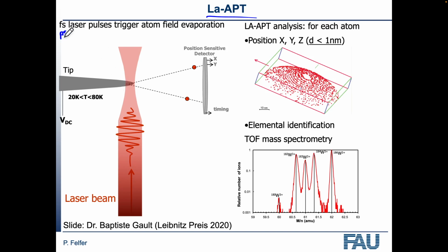People have tried whether femtosecond or picosecond lasers make a difference, and it doesn't seem to make a difference up to lower picosecond levels, because the heating and cooling times are in the nanosecond range anyway, so it doesn't make much of a difference. We have found if you go to very low femtosecond and attosecond, then it starts to make a difference, but not in the range that you can typically buy lasers in. So the laser that we have in our commercial atom probe, it's around 10 picoseconds in the LEAP. That's our commercial atom probe that we have.